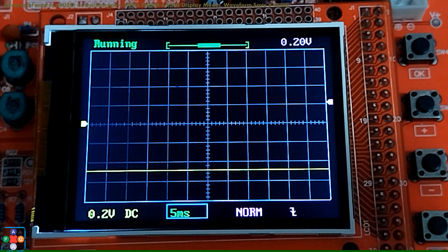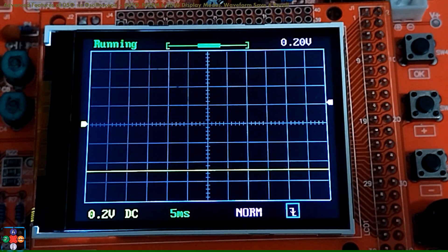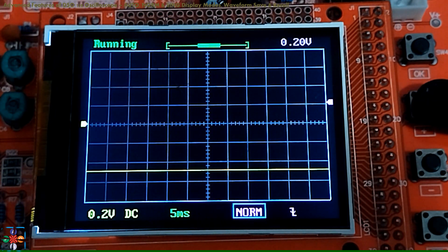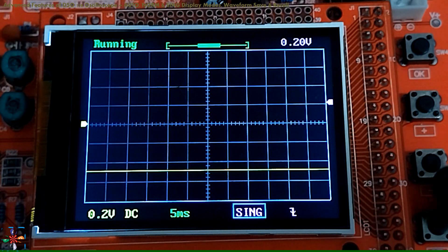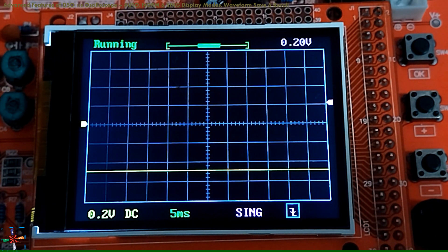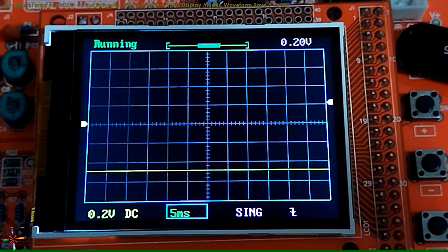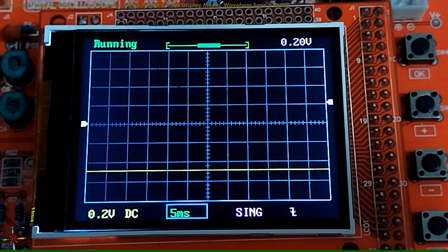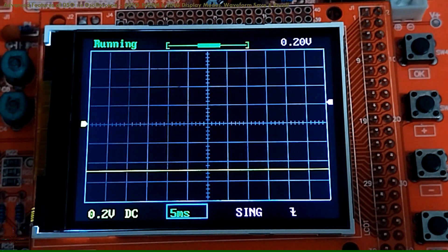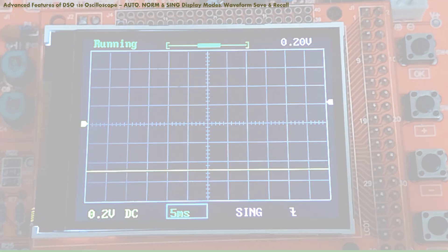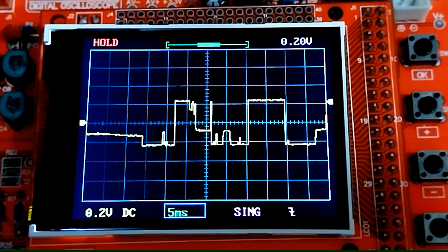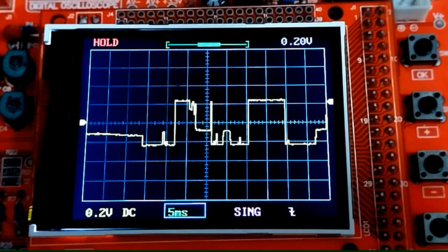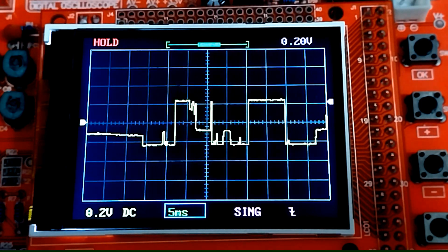When using single mode, you will initially set the oscilloscope to this mode without providing any signal. Begin by using the select push button to set focus on the second icon from the right at the bottom of the screen, then using the plus push button change the icon appearance to single. Make sure your display is not paused — if it is, push the OK button to resume display. For now there is nothing on our display. Now let's provide an input signal and watch what happens.